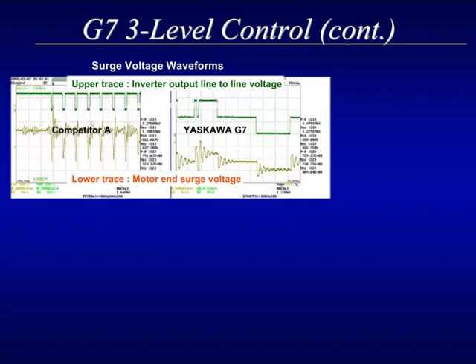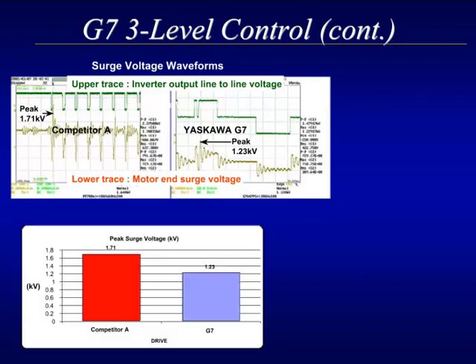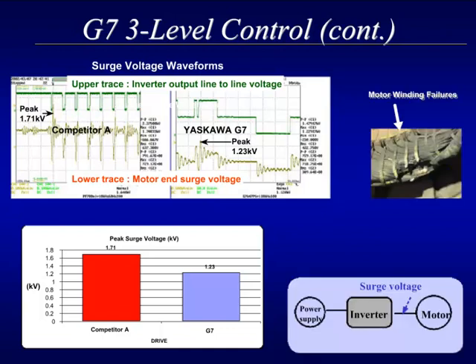In actual laboratory tests against a competitive 2-level drive, the worst-case surge voltages of each drive were captured and compared. The competitive drive was a recently introduced product with reflective wave software enabled. The competitive drive has a measured peak-to-peak voltage value of over 1700 volts, as compared to the G7, which has a peak-to-peak value of only 1230 volts. This data shows that the G7 generated peak voltages 28% lower than that of the currently offered 2-level drive. Motor winding failures, such as that shown in the photo, are much less likely when using the G7.